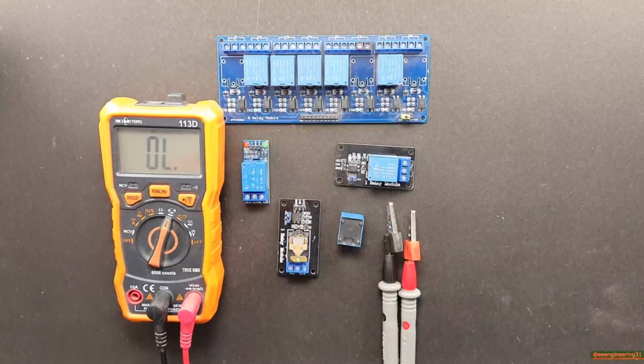You may see a resistance specified on the body of the relay. That's the coil's resistance, and you can calculate the current using Ohm's law. If the voltage is 12 volts, for instance, and the resistance is 500 ohms, the current that will pass through the coil is 12 divided by 500, or 0.024 amps, or 24 milliamps. As long as that's somewhere near the original part used, it should work fine. It's also okay to use a relay that takes any amount less current than the original. If the new one takes a lot more, it could overheat the transistors driving it.